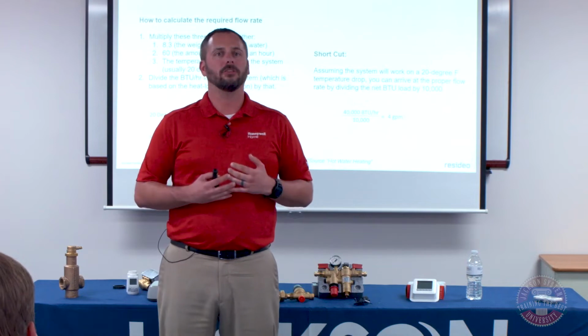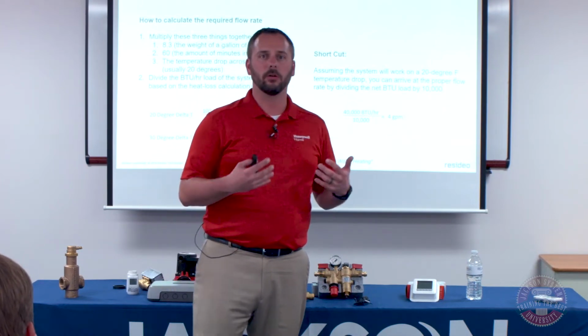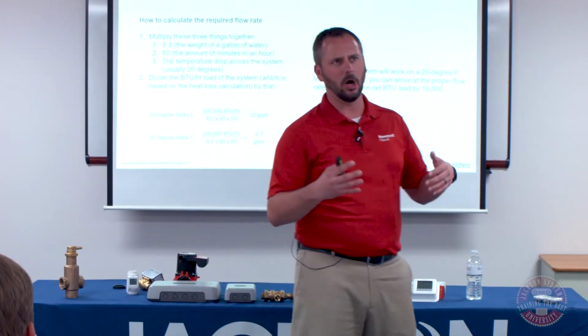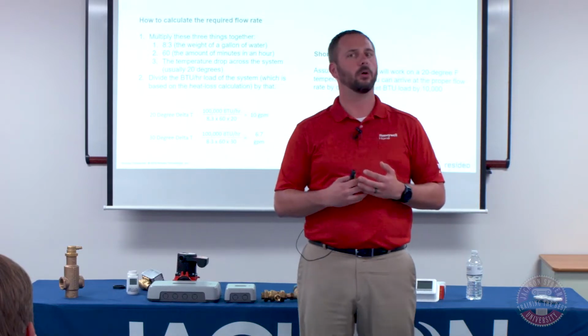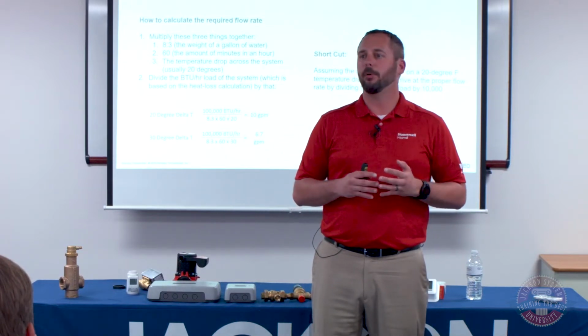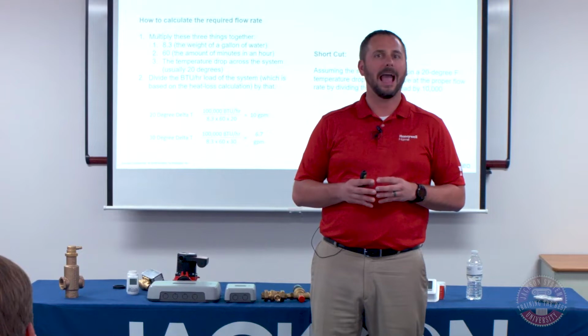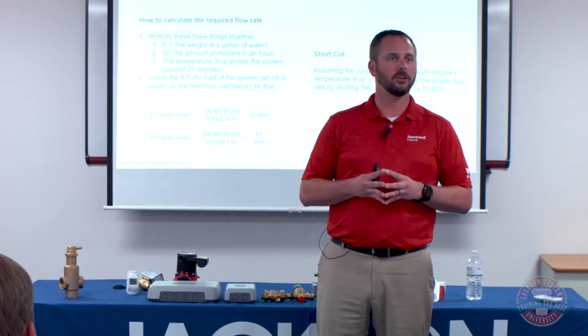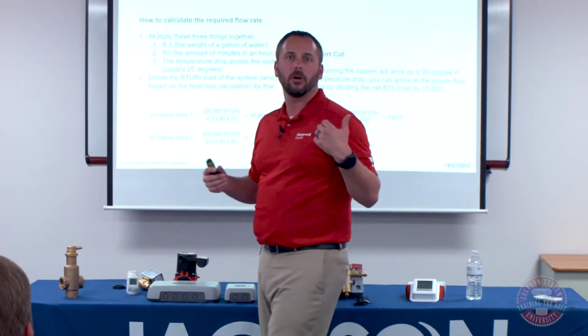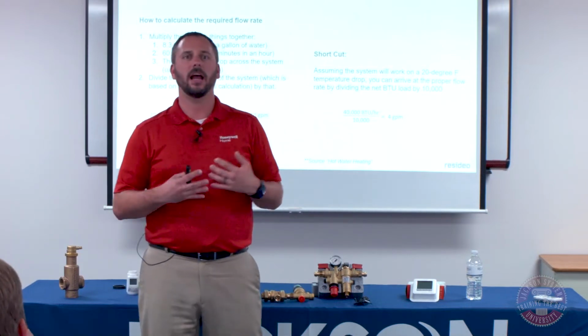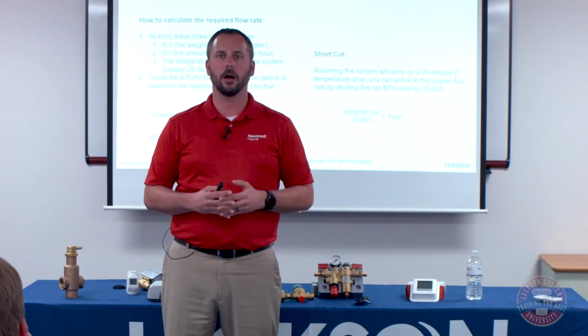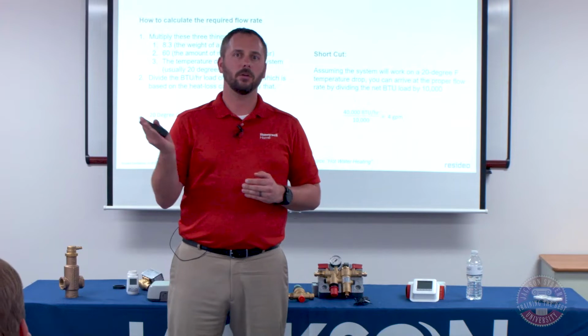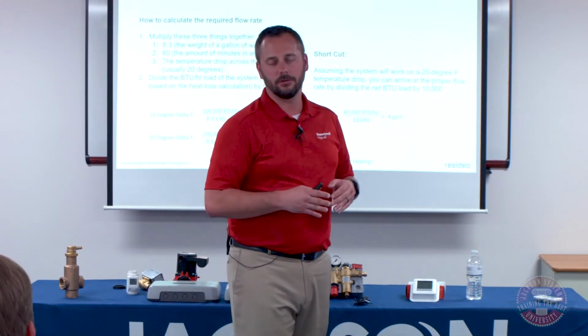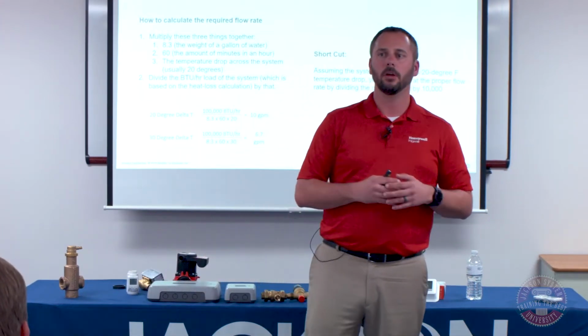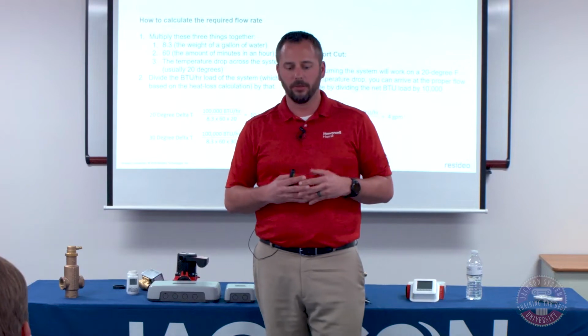So what we've got is, let's just say we have a 100,000 BTU boiler that's there. Actually, I'm going to go up. Let's say we've got a 120,000 BTU boiler. You don't need to look at the input rating on the boiler. You need to look at the output rating, because that's how much energy is actually being produced. So if you look at that boiler that's in there, let's just say hypothetically the output is going to be 100,000 BTUs. If you divide it by 8.3 times 60 times 20, you're going to come up with 10 gallons a minute.